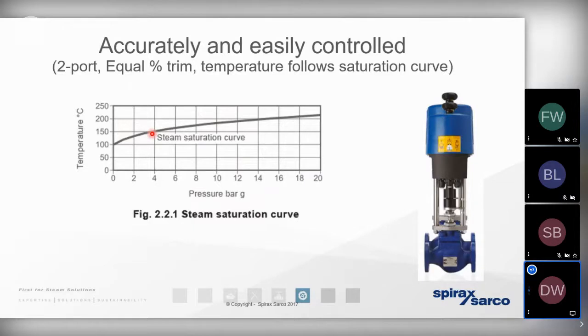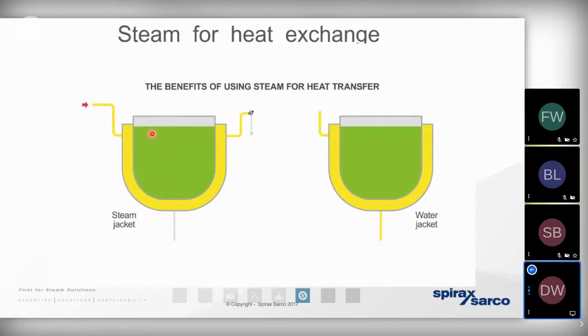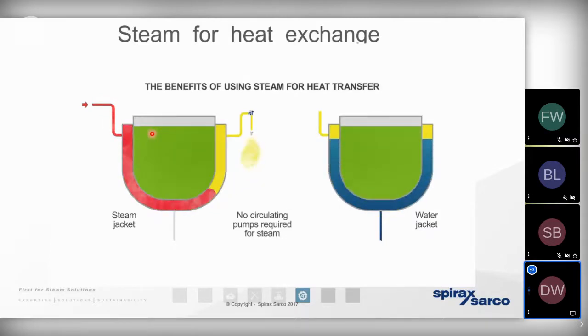So I just want to talk now to show how all of those key benefits can pull together in one little graphic here. If we look at the GIF image, this really reminds us that one of the first things we want to do is to ensure that the air is vented away from the system. We can get the air out of a steam using system by simply using the steam pressure to push the air across a thermostatic valve, at which point we can bring the process up to temperature very, very quickly.